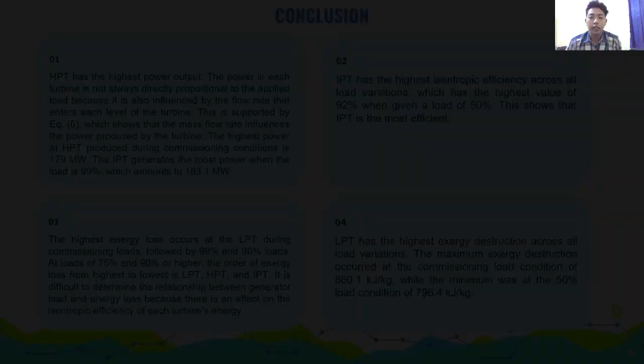Then, conclusion. This is the first conclusion. The high pressure turbine has the highest power output. The power in each turbine is not always directly proportional to the applied load because it is also influenced by the flow rate that enters each level of the turbine. This is supported by equation 6, which shows that the mass flow rate influences the power produced by the turbine. The highest power at the high pressure turbine was produced during commissioning condition, with a value of 179 megawatt. The intermediate pressure turbine generates the most power when the load is 99%, which amounts to 183.1 megawatt.